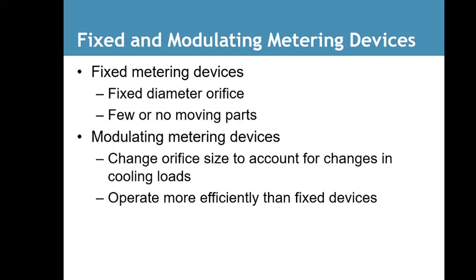The problem overall with the fixed orifices, they do not have the high efficiency level that you get with a thermal expansion valve. It's always the same. It always lets the same amount of refrigerant through it. So some refrigerant gets wasted in these cases. A modulating metering device changes orifice size to account for the change in cooling load. It opens and closes. It just operates better. It's more efficient. But they are problematic. They can go bad. A fixed orifice device will never go bad. It will always work as long as the refrigerant going through is clean.